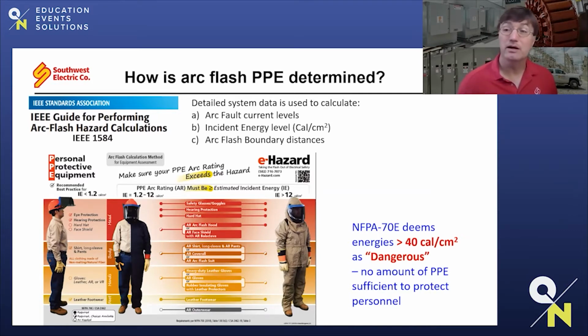The NFPA 70E points out that any energy level above 40 calories per square centimeter is considered dangerous. No amount of PPE is sufficient to protect that individual at energies above 40 calories per square centimeter. That's not only because of the heat and flame, but also for the sheer force of shock, the amount of shrapnel that could be jettisoned during events of that nature, as well as the amount of toxic fumes that can be generated. So that's important to know as we go through this: 40 calories is the cutoff. Beyond that, you really don't need to be exposed or have any of your employees exposed to energies that high.